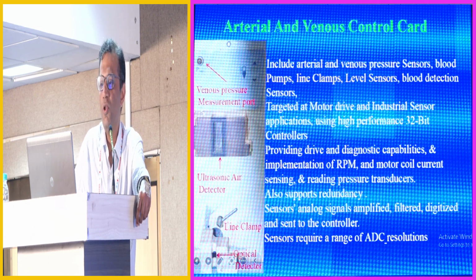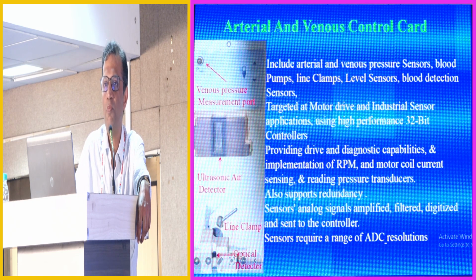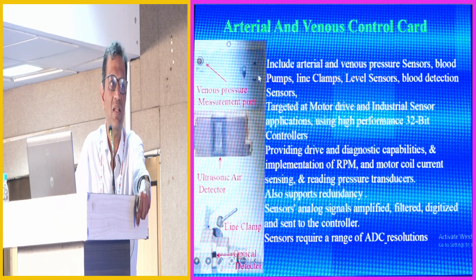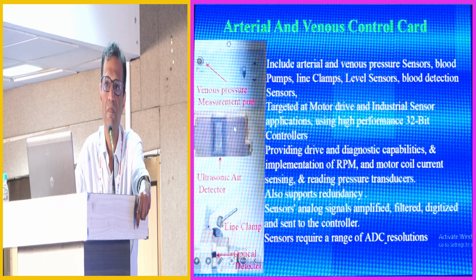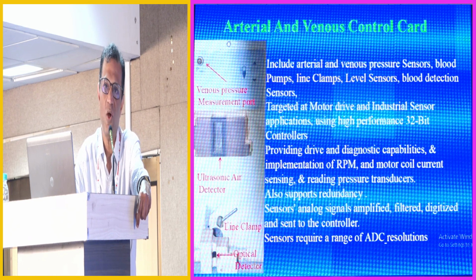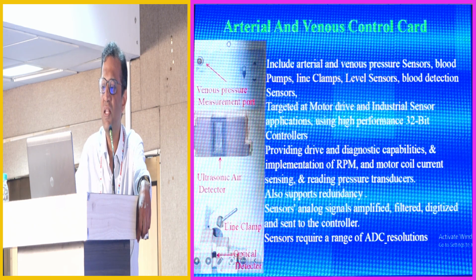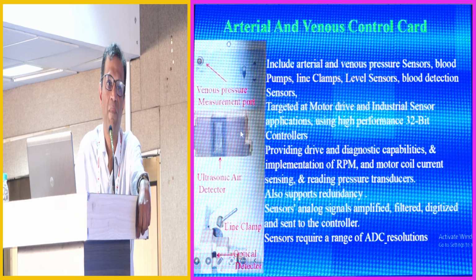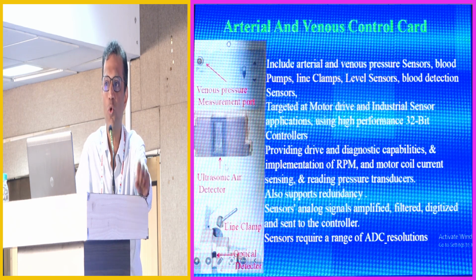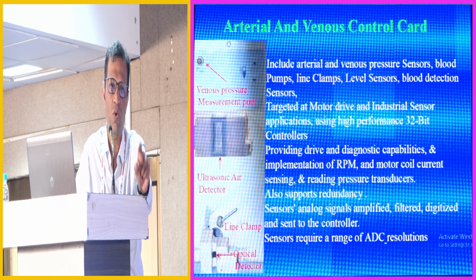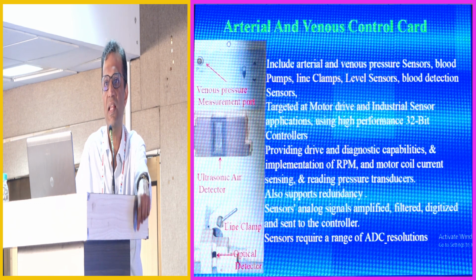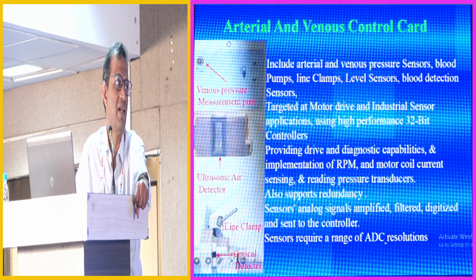Now, this is what the machine also has on the return side. It has a venous pressure port here, and these two arrows which allow us to adjust the level of blood in the venous bubble chamber. It has an ultrasonic air detector over here, which is based on the principle that sound travels fastest in solids or in semi-solids, blood, which is actually a colloidal solution, a little slower in liquids and slowest in air. So on either side of this air detector, we have a piezoelectric crystal which generates ultrasound waves on one side and detects the velocity of the wave passing through the blood column on the other side. And should the velocity fall below a threshold which we set on the machine, then it will detect that there is an air-blood mixture.